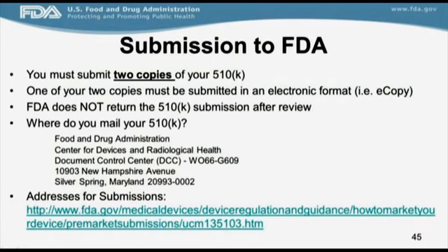The FDA does not return your 510K submission after its review, so you will not get back the hard copy. When you mail your 510K, please make sure that you mail it to the appropriate document control center, the address provided on this slide. For additional references, you can refer to our addresses for submissions link that is also provided on this slide.